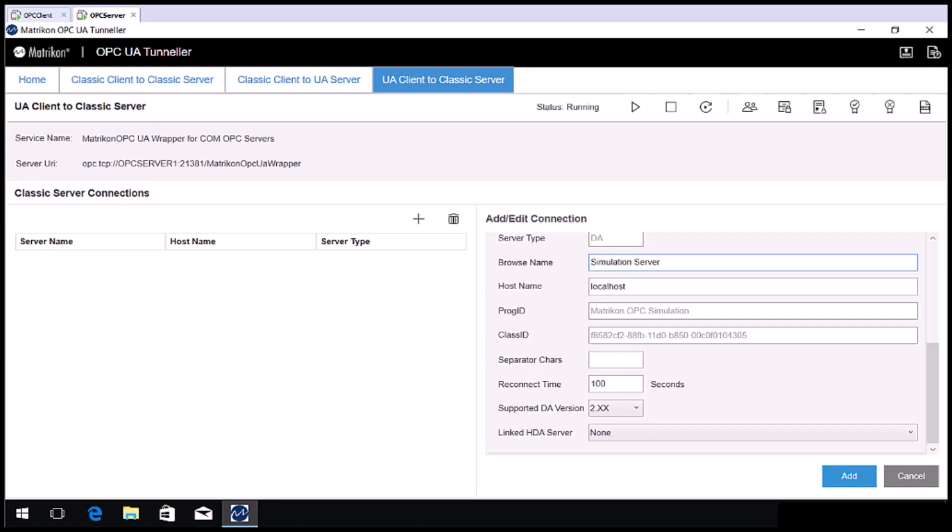This will appear as a folder in the OPC UA client. The separator chars field is designed to speed up browsing. In this case, I know that the simulation server uses full stops in the tag names, so I'll put a full stop in here. Note, you can add as many separator characters as you like one after the other if your OPC server uses more than one type of character between items.